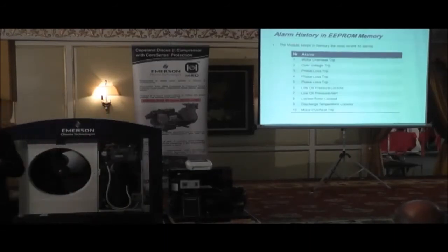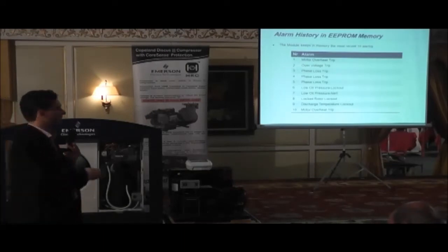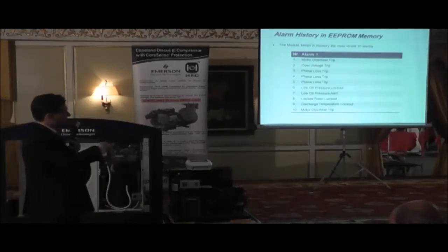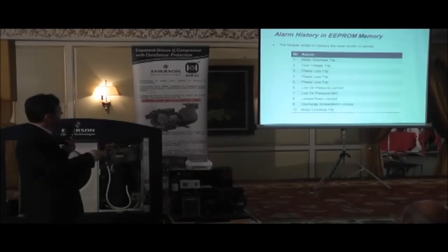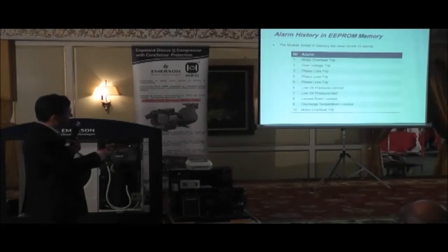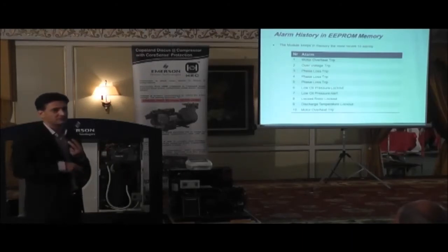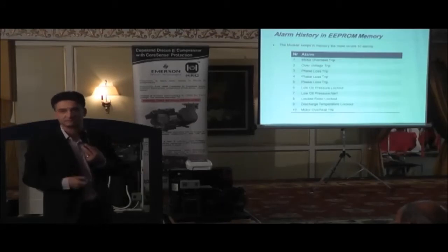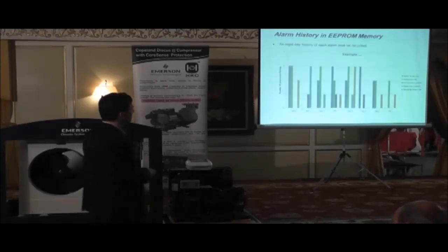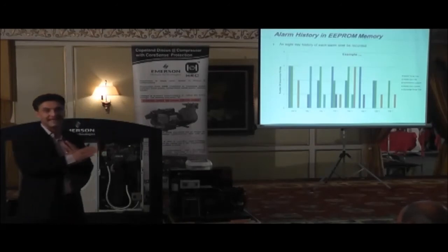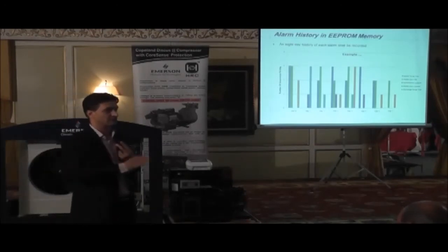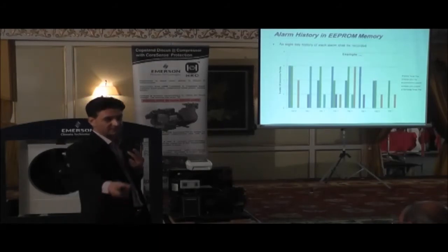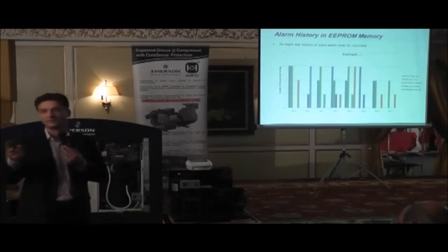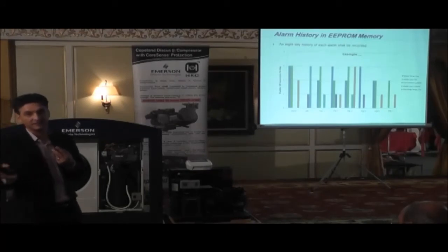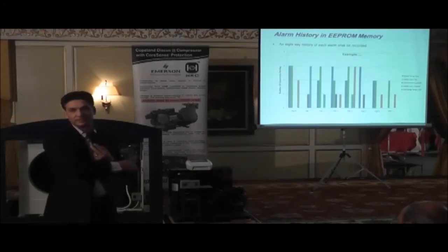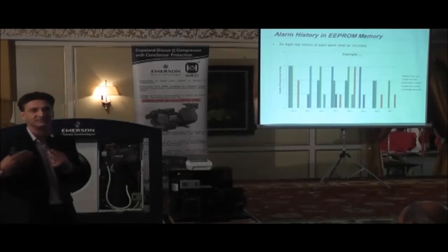So this is just an example. When you connect your PC and you go to display number 1, it will tell you what the 10 most recent trips are. Okay. So this is the most recent, then you had an overvoltage, phase loss, low oil pressure, etc. So this will tell you exactly what's been happening in the system. The next screen will give you an 8-day alarm history. Okay? So now if you connect your PC to the compressor, you will know how many trips you've had, what trips you've had in the past 8 days of operation. Okay? This information can help you diagnose if there's any system problems.